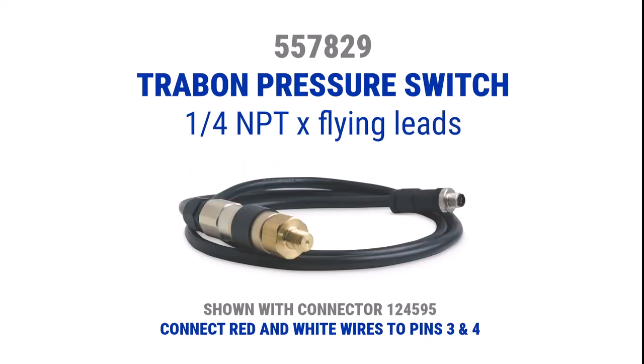557829 is popular with some older distributors because it has been around a long time and they are familiar with it. When it's new, it has 3 wires, but only 2 wires are needed when used with a G3. So the black wire should be clipped off and the red and white wires connect to pins 3 and 4 on the M12 connector. Polarity doesn't matter.